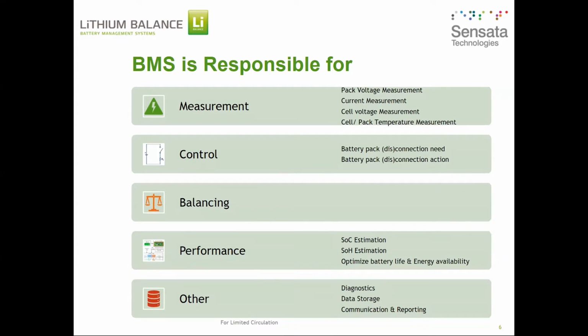Coming back to the control side, we discussed MOSFETs and DC contactors. There's no clear demarcation of at what point MOSFET will be preferred versus DC contactor, but the generic trend is: at low current applications we go with MOSFET. Typically, anything beyond 200 amperes we recommend DC contactor, and anything less than 200 amps is MOSFETs. Now the third function is balancing.